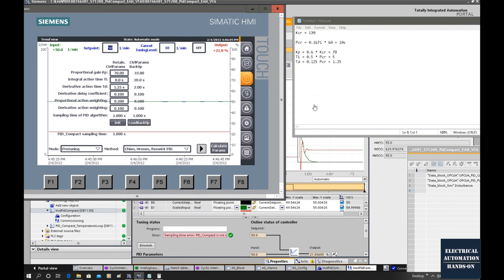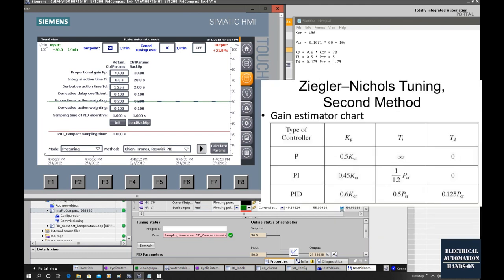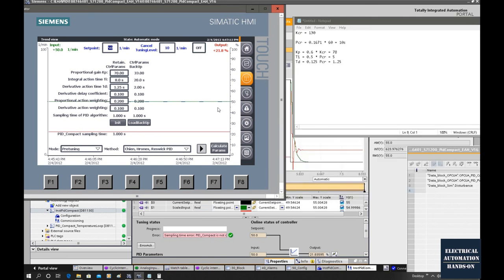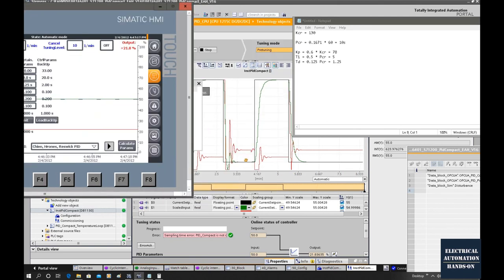Using the Ziegler-Nichols second method, we run the PID in auto and increase the gain until the system gets oscillation. At that time, we record the gain KCR and the PCR value. After this, we use this chart to calculate Kp, Ti, and Td, then type those values into our PID controller. From this actual test, we can see these values are running very well. Basically, we just need to do a little bit of fine tuning and this process achieves very good performance.